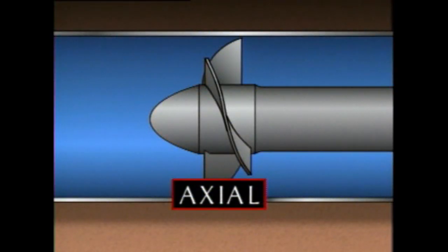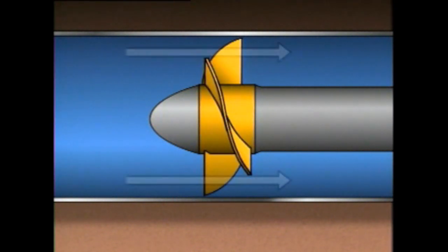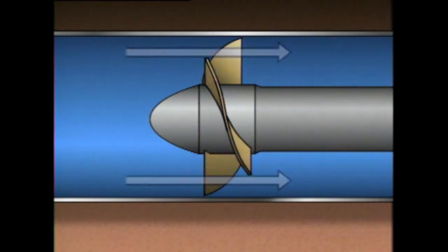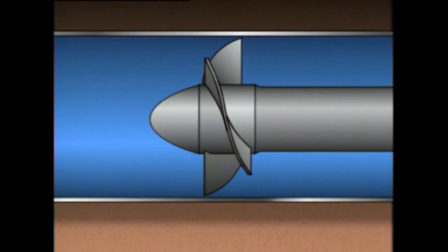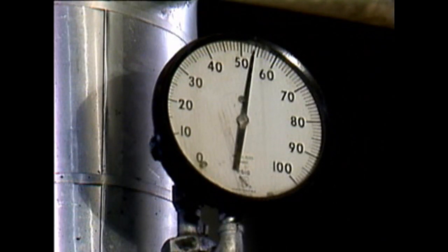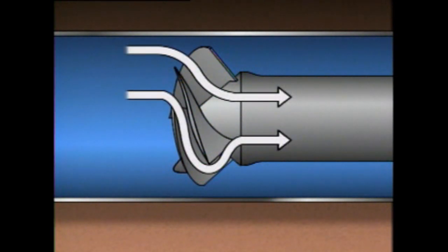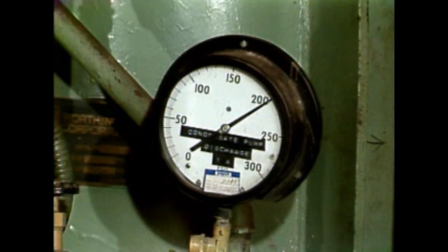In centrifugal pumps with an axial flow design, the impeller moves the liquid through the pump along a path parallel to the pump shaft. The liquid is moved mainly by the propeller action of the impeller's vanes, using only a small amount of centrifugal force. As a result, the discharge pressure of an axial flow pump tends to be lower than that of a radial flow pump; however, an axial flow pump may be able to move large quantities of liquid. Mixed flow pumps combine the characteristics of both, using centrifugal force and propeller action to develop a relatively high discharge pressure while still moving a large quantity of liquid.